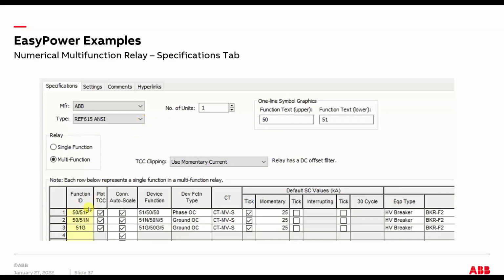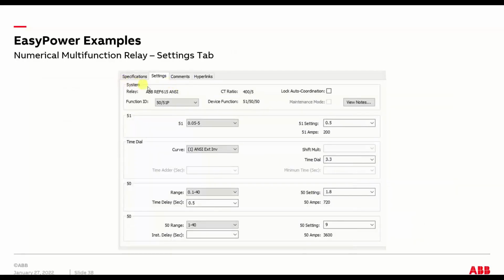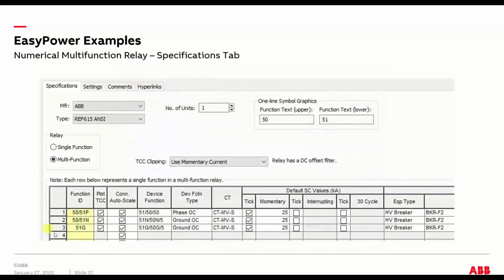Here's your type. This one's multifunction, so you can add in as many functions as you want to have turned on in a relay. So this one's really basic. It's got an instantaneous and time overcurrent phase, same for the neutral, and then a time overcurrent for the ground. And then here's the details on it: you have basically four devices in one.